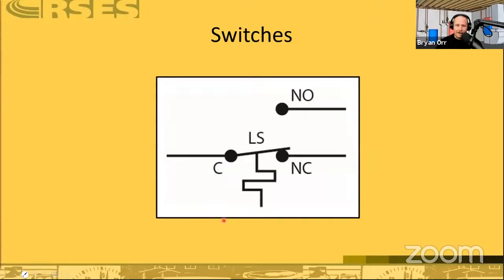On this one we've got a single pole double throw, temperature activated switch, so it's normally closed in one position and normally open in the other. This is where it gets tricky, because a switch isn't always just normally closed or normally open. In this case, it's normally closed to the bottom position and normally open to the top position. So as the temperature rises, it's going to make to that top position, and this would be a limit switch or a fan control.